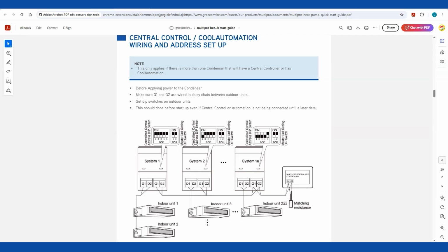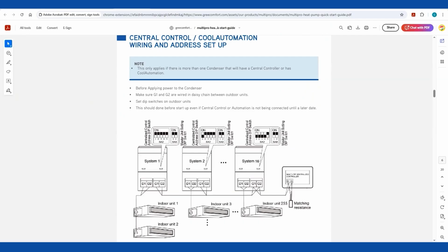If you do them all separately and then you want to combine them as far as central control or cool automation goes, you're going to have a problem. Say system 1 was all by itself. You commission that unit, it's going to address them more than likely 1, 2, 3, 4. And then if you do system 2 standalone all by itself, it's going to address them 1, 2, 3, 4. So when you try to put central control or cool automation in, you've got duplicated addresses and it's going to give you a fault.